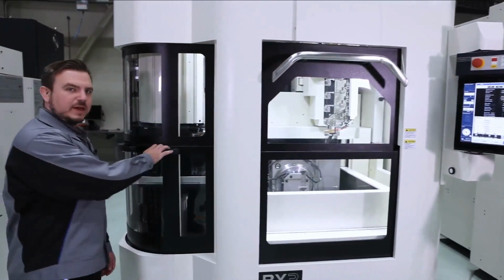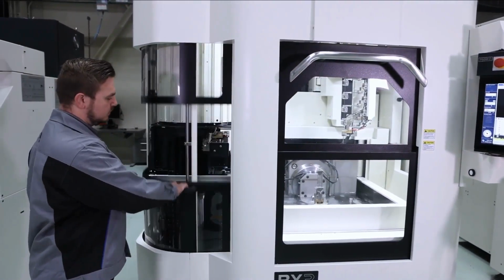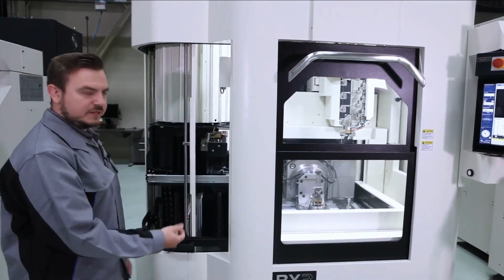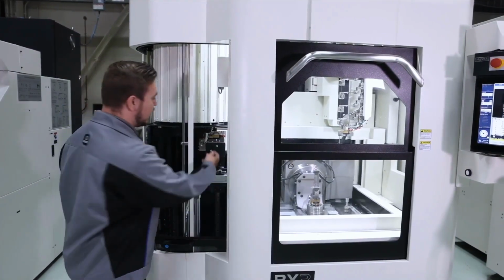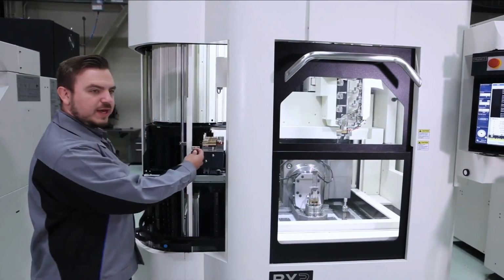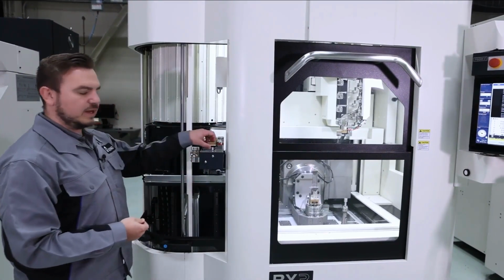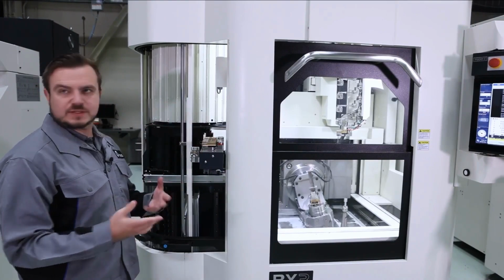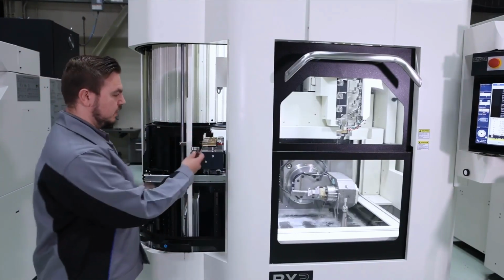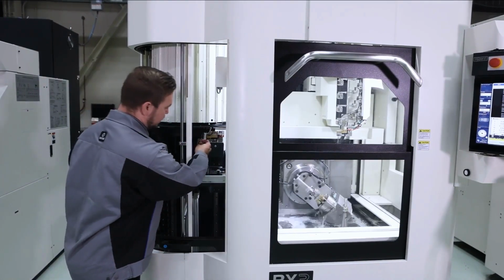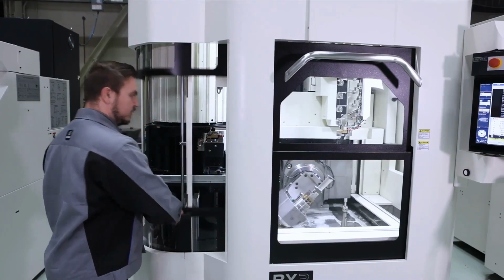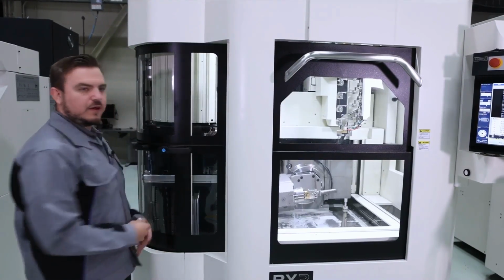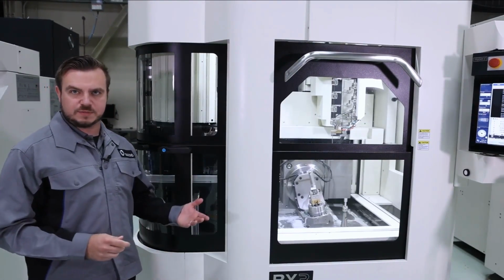So over here, I can open the carousel door. And if I need to inspect a guide or replace a guide, I have full access to the AGC, and I can pull out the guide, replace it, inspect it, and I'm able to push this back in, close the door, and all that was executed while the program is being run.